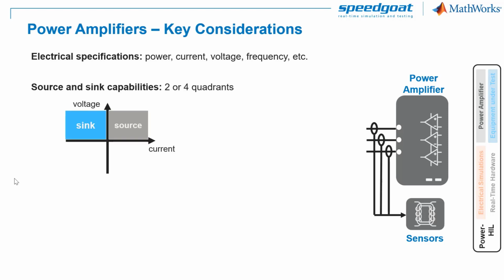Second, the source and sink capabilities to be able to act as a load and as a power source. This is typically referred to as 2 or 4 quadrant operation. You'll typically require only 2 quadrants for sourcing and sinking DC, as voltages will not change sign. But you'll need 4 quadrants for sourcing and sinking AC power.